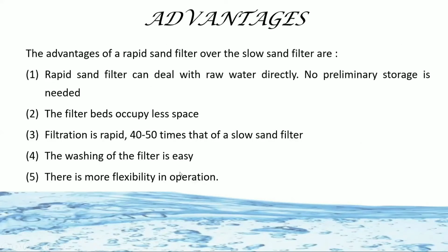So what are the advantages of the rapid sand filter? The rapid sand filter can deal with raw water directly. There is no need for storage, which is required in the slow sand filter. The filter beds occupy less space. Filtration is rapid, almost 40 to 50 times that of the slow sand filter. The washing of the filter is easy.